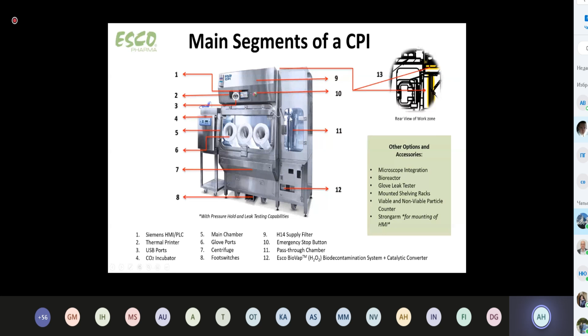Next, I would also like to share with you that the dimensions of this isolator are actually going to be important to share with the customer. If you look at this diagram here, I want you to focus on the plan view. From left to right, if you include an incubator, the main chamber and the pass-through chamber, the average left to right length that you need in the lab is more or less maybe 3.8 to 4 meters. From front to back, you will need about 1.06 meters. Of course, there will be some space at the back for maintenance purposes, but this will be the dimension that you will be having more or less for an incubator.